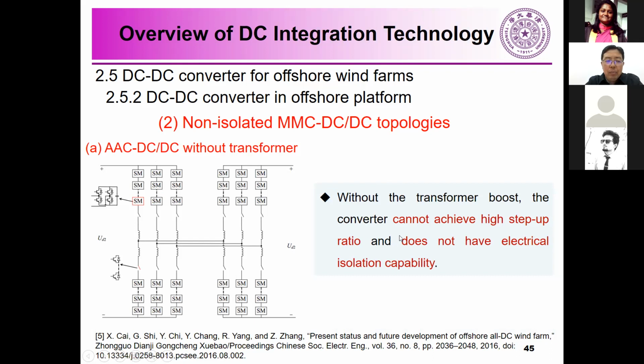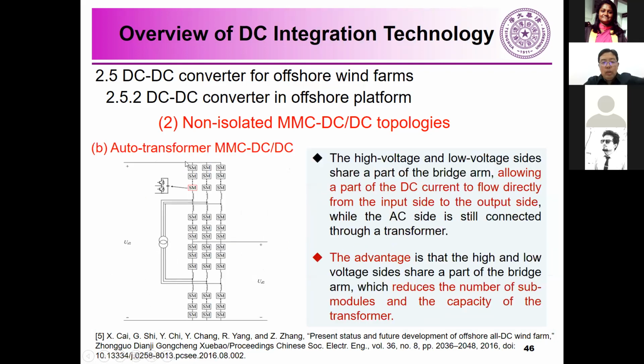Another type is the auto-transformer DC converters. In these solutions, the high voltage and low voltage sides share a part of the bridge arms, allowing a part of the DC current to flow directly to the output side, while the AC side is still connected through transformers. The advantage is that sharing bridge arms reduces the number of submodules and the capacity of the transformers, lowering the cost.